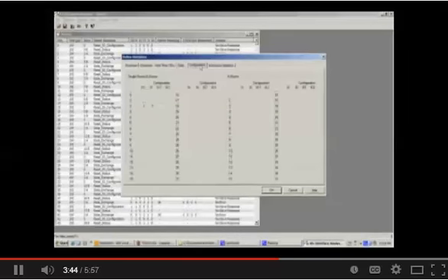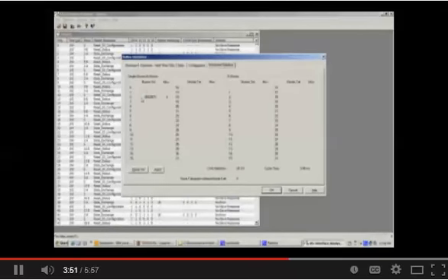And then if I go to the configuration tab here, I also get some diagnostic information for that particular slave. And then on advanced diagnostics here, I'm monitoring the number of messages that have been sent. Now notice that there are no missed messages at this time. So if I go jiggle or loosen the connection here to this particular node, as such, you'll see that I can generate a number of missed packages there. So if I go ahead and just take it on and off real quick again as well, you'll see there that I've got missed packages, missed messages also occurring.